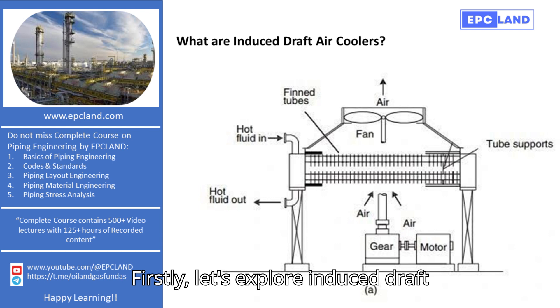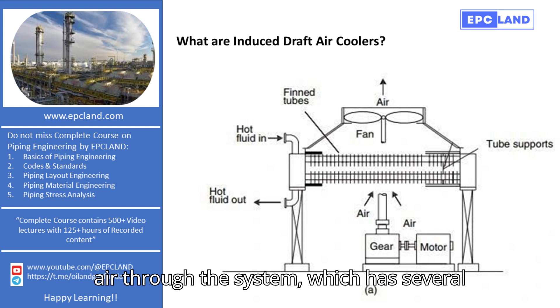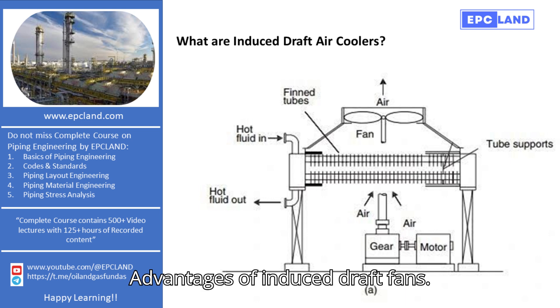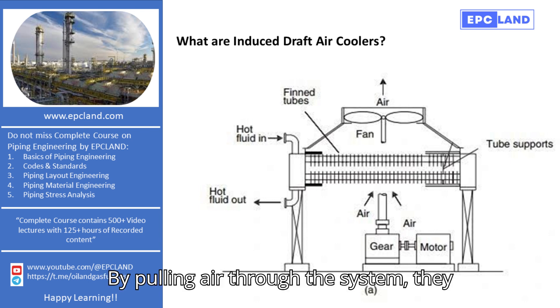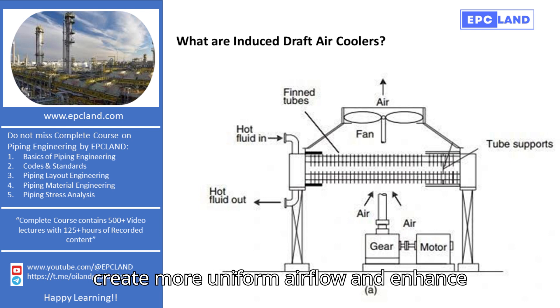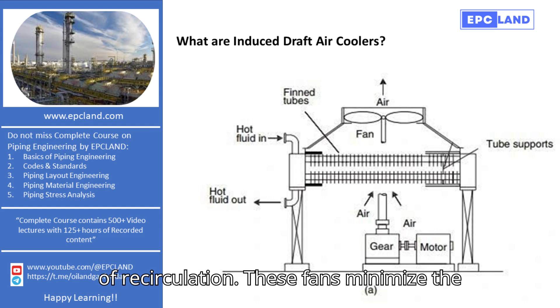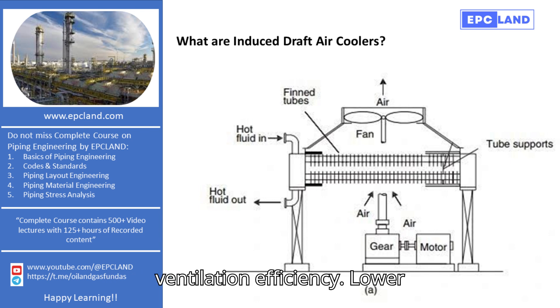Let's explore induced draft fans. These fans are designed to pull air through the system, which has several advantages and a few disadvantages. Advantages of induced draft fans: Higher efficiency — induced draft fans are generally more efficient at moving air. By pulling air through the system, they create more uniform airflow and enhance overall performance. Reduced risk of recirculation — these fans minimize the likelihood of recirculating hot or contaminated air, improving cooling or ventilation efficiency.